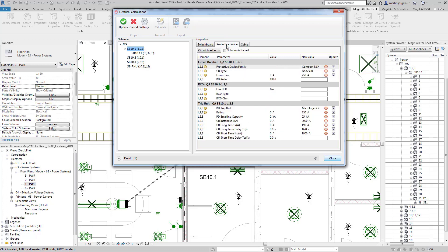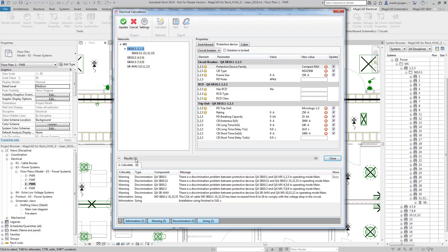So here we can see the protective device that the calculation engine has selected for this particular circuit and underneath here we have our results. Now we do have some warnings here about discrimination problems but this is due to the method that's been used to calculate this. Essentially we have one final load on each distribution board and the protective device for that load will conflict with the protective devices protecting the circuit. However we're not interested at this point in time in these particular circuit breakers because ultimately that will be broken down into separate individual loads. So the sizes that we're interested in are the sizes of the breakers that are supplying power to the distribution board.